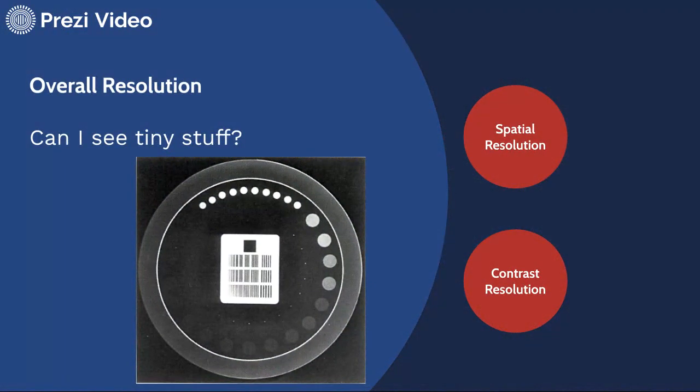What we're talking about when we talk about resolution is just the question, can I see tiny stuff? These types of phantoms are helpful for looking at that tiny stuff. If we're looking at spatial resolution, we're oftentimes looking at these little line pairs at the center of this phantom. If we're looking at contrast resolution, we're looking at these gradual shifts from white through gray to black in these small circles around the outside of the phantom.